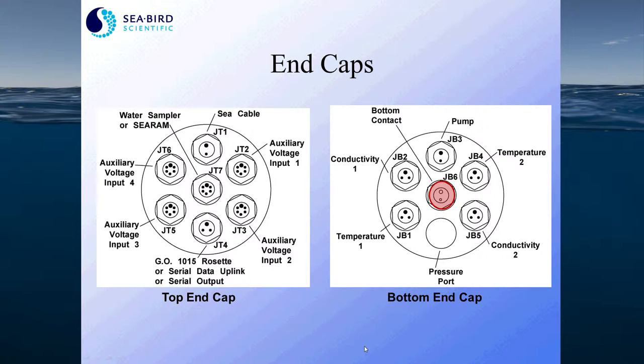The top end cap also has connectors for the Sea Cable, the G.O. 1015 water sampling device, and a center connector that allows you to attach an SB 17 Plus, which is a memory power module for the 9 Plus, a remote instrument, or an SB 32 water sampler.